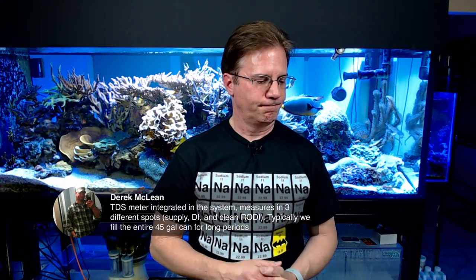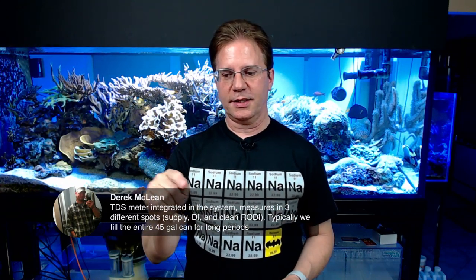So once you've got your barrel of oxygenated RO water, you're going to use what is the term? It's a certain type of pump, a permeate pump, to move the water out of the RO barrel through the DI and into the DI barrel. And by doing this, your DI is going to last much, much longer, and you're going to save money.